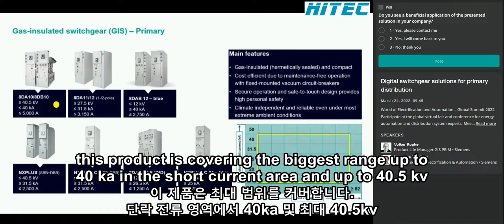Please find the following switchgear type of our GIS primary family at this overview. For example, we have here the 8DA10, 8DB10, that means single busbar, double busbar. This product is covering the biggest range, up to 40 kA in the short current area and up to 40.5 kV.